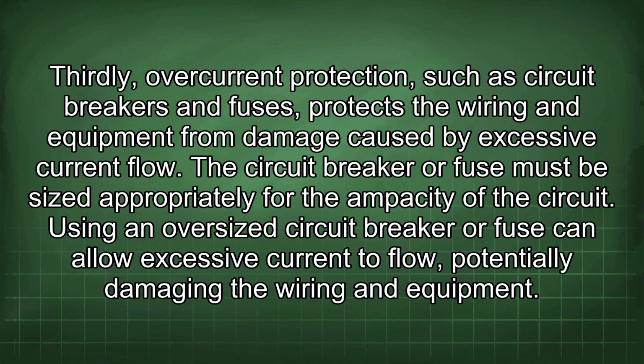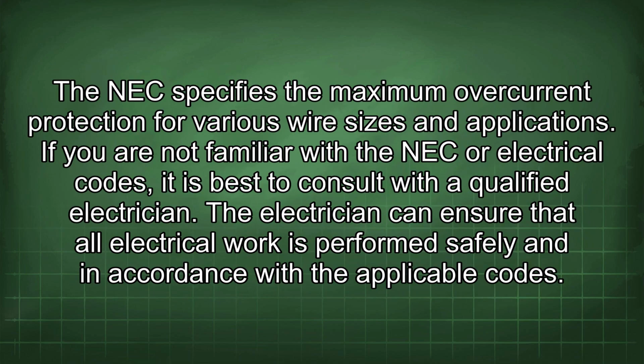Thirdly, overcurrent protection, such as circuit breakers and fuses, protects the wiring and equipment from damage caused by excessive current flow. The circuit breaker or fuse must be sized appropriately for the ampacity of the circuit. Using an oversized circuit breaker or fuse can allow excessive current to flow, potentially damaging the wiring and equipment. The NEC specifies the maximum overcurrent protection for various wire sizes and applications. If you are not familiar with the NEC or electrical codes, it is best to consult with a qualified electrician. The electrician can ensure that all electrical work is performed safely and in accordance with the applicable codes.